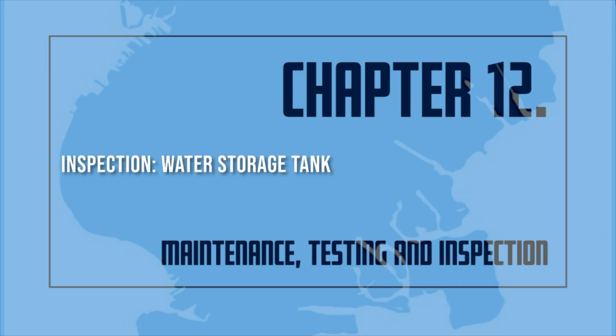C. Water storage tank. Condition of water in tank. Water level. Tanks without supervised water level alarms at constantly attended locations shall be inspected monthly. Tanks with supervised water level alarms at constantly attended locations shall be inspected quarterly. Water temperature. The temperature of water tanks shall not be less than 40 degrees Fahrenheit. The temperature of water in the tanks without low temperature alarms connected to a constantly attended location shall be inspected and recorded daily during the heating season.